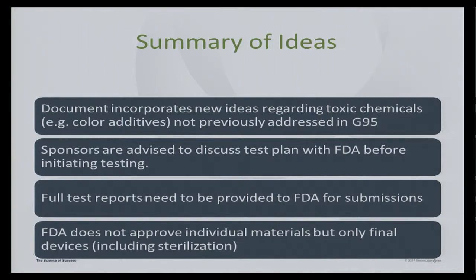This is one that we've seen, and I've actually really recommended. Sponsors are advised to discuss the testing plan with the FDA before initiating testing. And I recommend this if you're looking at doing something that might be a little bit more risky. If you're looking at justifying out of testing, if you're looking at maybe doing less testing, or if you're not just checkboxing, what we can do is get together a test plan. We can talk about your product, its intended use, its materials, and get a proactive test plan together with the justifications in place, submit that to the FDA, and then they'll get back to you and respond to let you know if it's a correct plan or not.